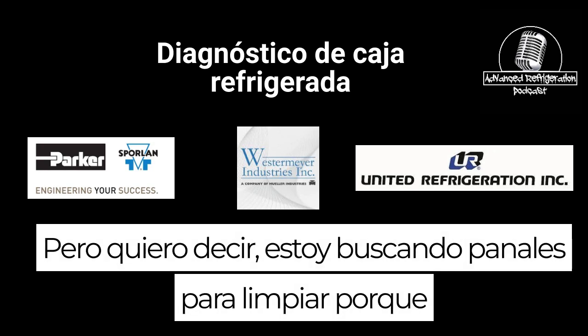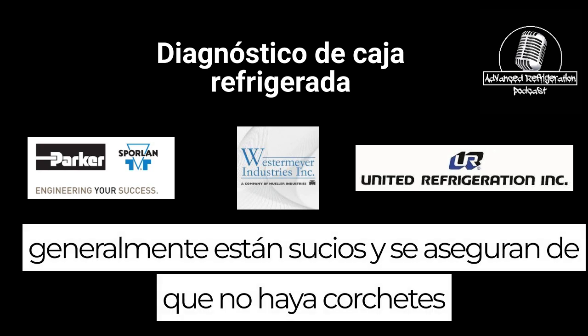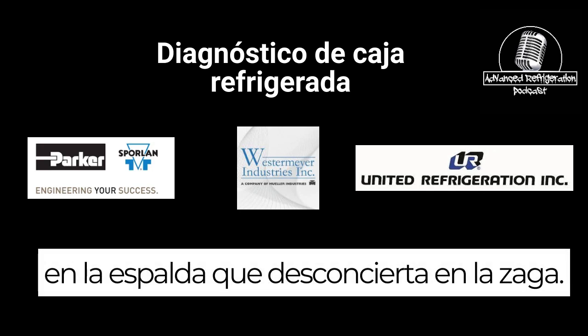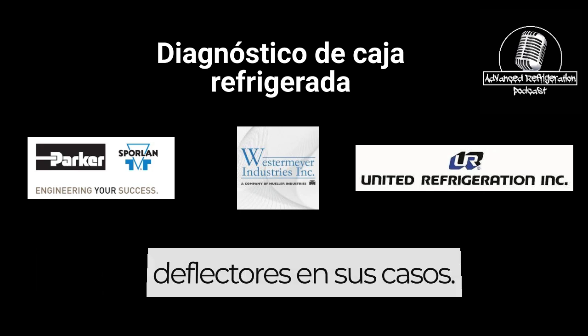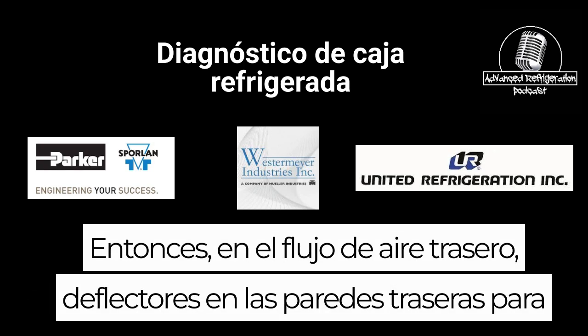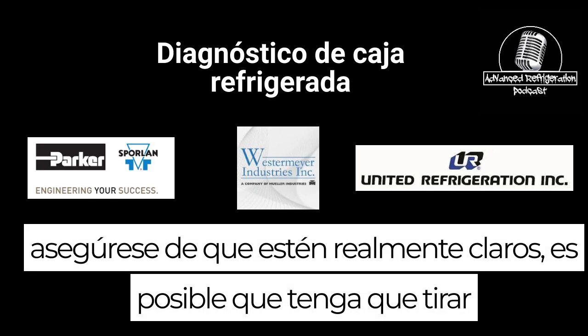I mean, if it's slow, I'm looking for honeycombs to clean because they're usually dirty, and making sure that there's no brackets in the back, that baffles in the back. Hill Phoenix is notorious for putting baffles in their cases. So in the back, airflow baffles in the back walls, make sure those are actually clear and clean. You may have to pull them apart and clean them.